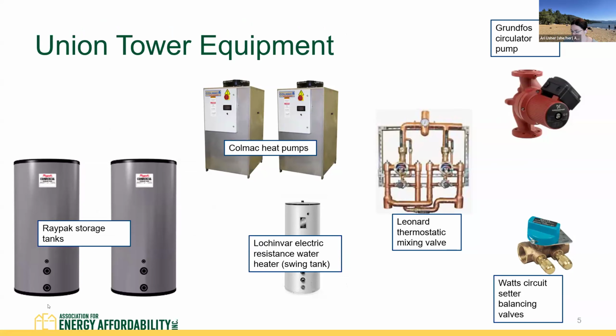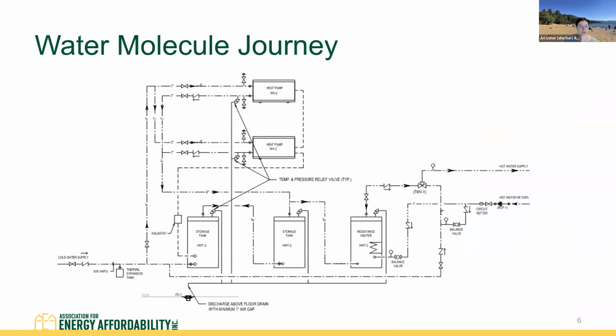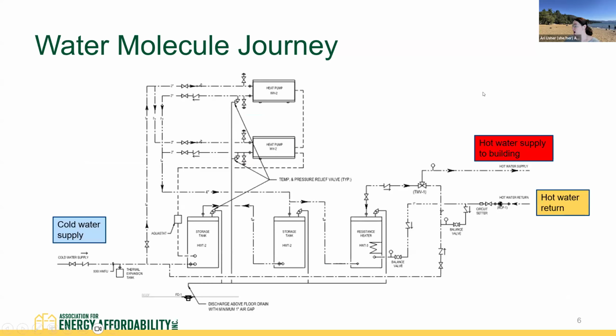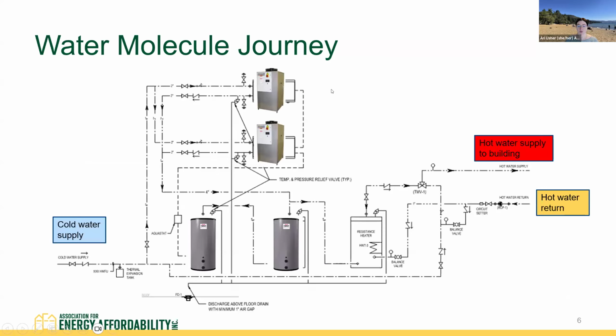So without further ado, what we're seeing here is a piping diagram. Let's go ahead and place ourselves in here. We've got the cold water supply to the plant coming in on the left side of the screen. It goes through that series of pipes that you see there and comes out as hot water supply to the building. And that's not all though, because we also have hot water returned to the plant from the recirculation. So let's go ahead and place the equipment. We've got the heat pumps up here. We've got our primary storage tanks. We've got our swing tank, mixing valve, pump, and finally balancing valves.